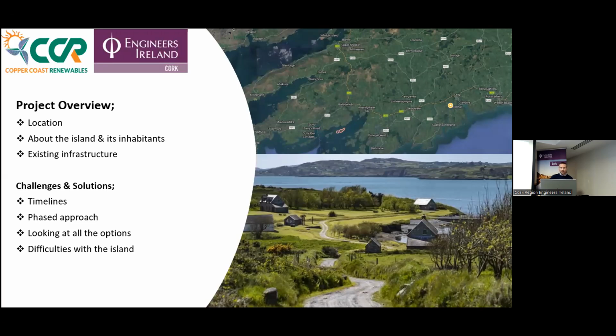Some of the challenges were the location and not being able to put wind turbines there due to planning concerns. Another issue was it was running on diesel generator 100% 24/7, but there were batteries left over from the wind turbines, running through charge controllers, charging deep cycle marine batteries, big ones at 80 kgs each. So they were powering the island with diesel generator backup, but once the wind went, the charge controllers were never recommissioned to run directly with the generators.